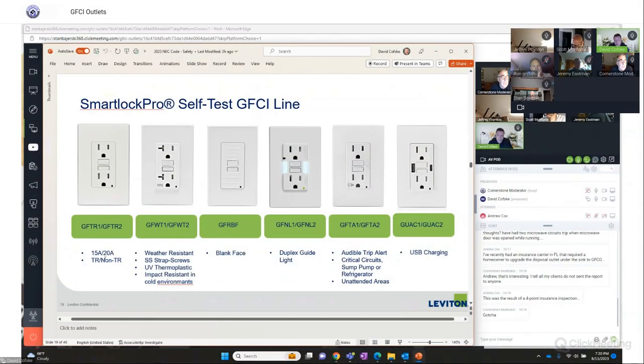Anything going into a residential application, it's basically the height off the floor, but those receptacles fall within that height requirement, so they must be tamper resistant. The next one is basically a weather resistant GFCI for outdoors. You can see down in the left hand corner there's a logo, WR. Any device going outside needs to have that WR symbol on it. If there's an inspector that's going to inspect the property and he doesn't see that WR symbol, he's going to basically make you pull it out and put one in.